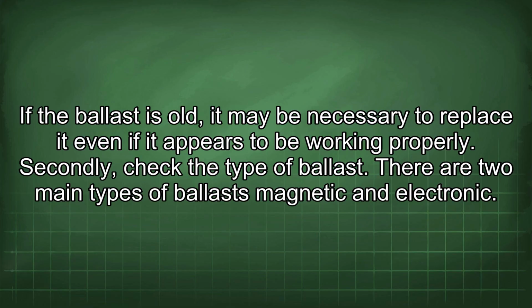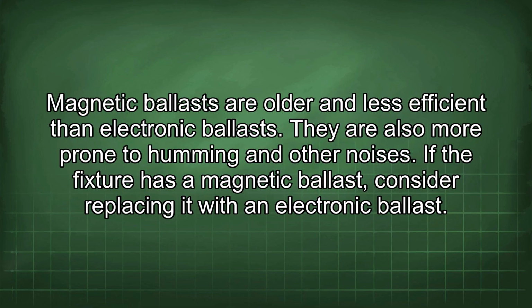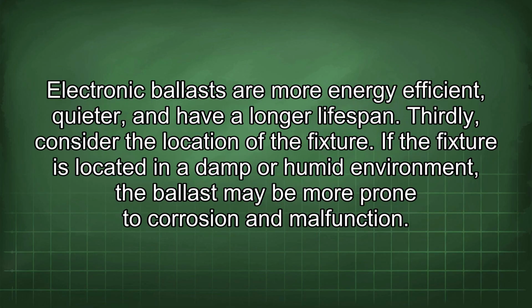Secondly, check the type of ballast. There are two main types of ballast: magnetic and electronic. Magnetic ballasts are older and less efficient than electronic ballasts. They are also more prone to humming and other noises. If the fixture has a magnetic ballast, consider replacing it with an electronic ballast. Electronic ballasts are more energy efficient, quieter, and have a longer lifespan. Thirdly, consider the location of the fixture.